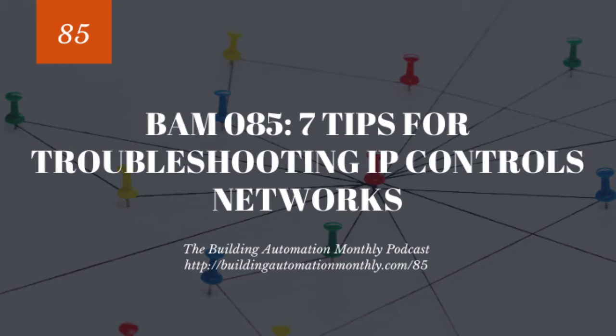The field trunk connects to the supervisory device, and the supervisory device takes all that data, converts it to whatever upstream protocol it's using, HTTP, IP, etc. Well, when you're using IP controls, you don't necessarily have the supervisory device doing that anymore, depending on the manufacturer you're with. And so now you're talking about a greater reliance on BBMDs, you're talking about routing, all sorts of other things. And like I said, we'll discuss that in tip 4, but you really have to understand those boundaries, both the physical boundaries of the network as well as the logical boundaries.